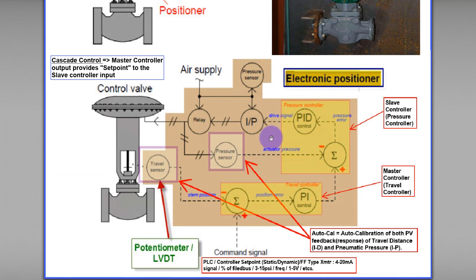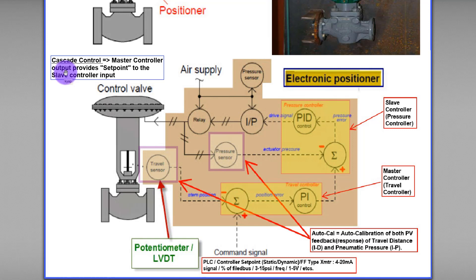Now let's talk about the positioner. There is a cascade control happening inside the positioner. Cascade control involves two controllers — one is the master controller and the other is the slave controller. The master controller output provides the set point to the slave controller input.